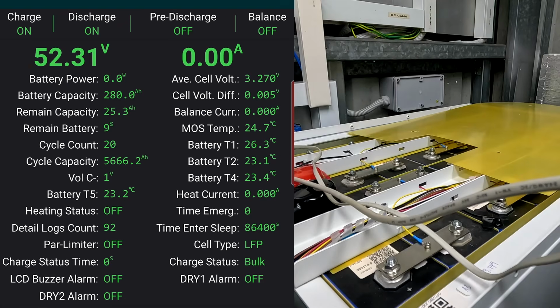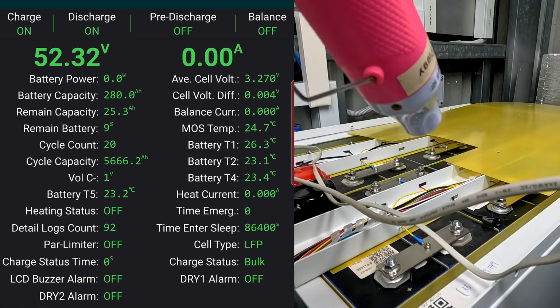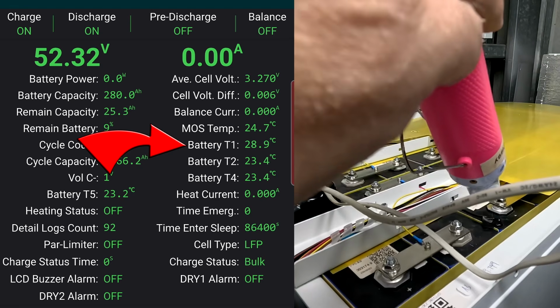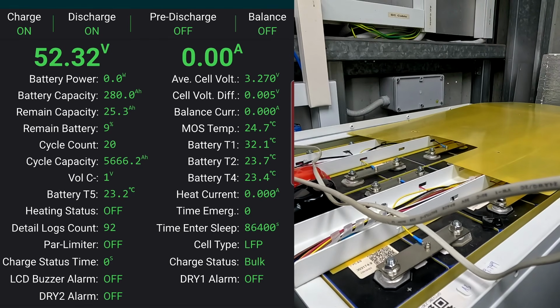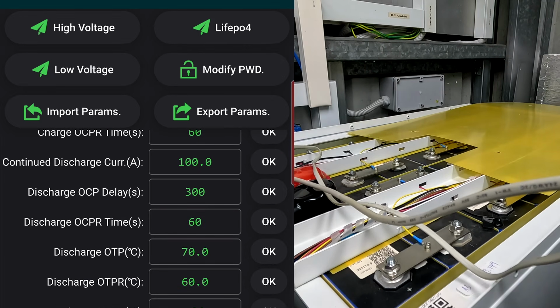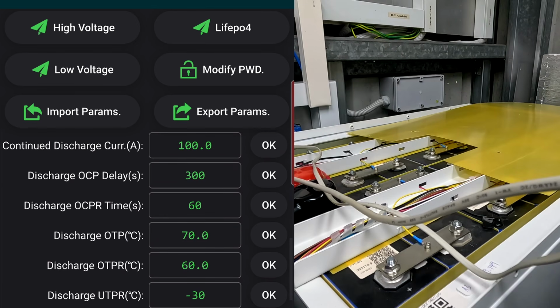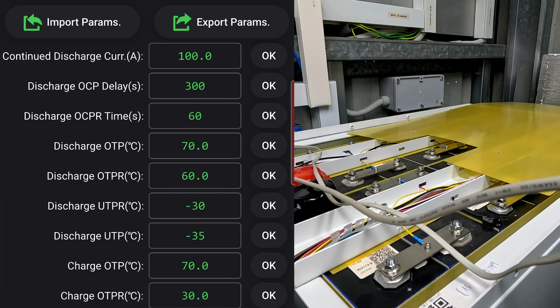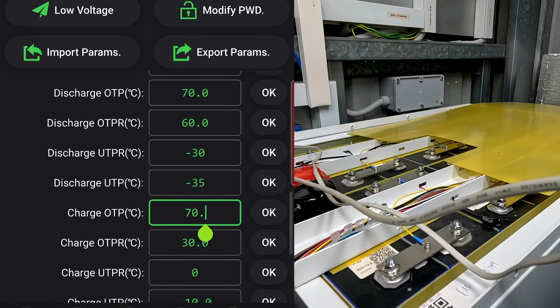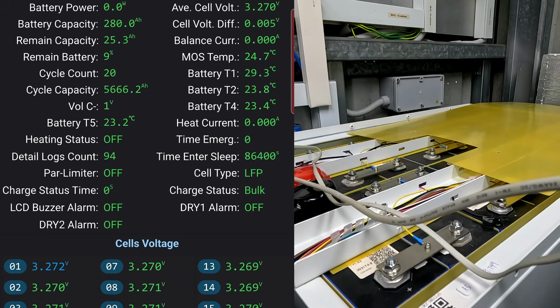Yes, we can. With our Miss Piggy. You should see T1. Yep, T1 is rising. Okay, that's temperature sensor number 1. Perfect. So we just need to set the limit correctly, and then we can trigger an over temperature warning. I'm just not sure if this actually reacts to it, because this is a charge over temperature warning 30. Okay, and the over temperature protection to say 40. Okay, and then we go back in the BMS and see what we can trigger.